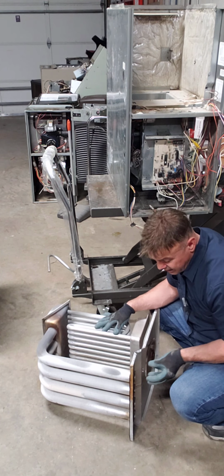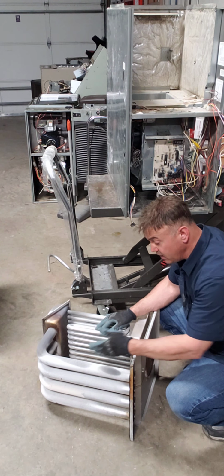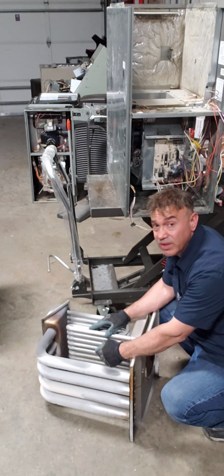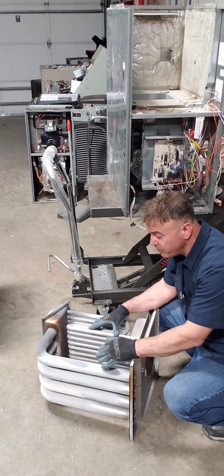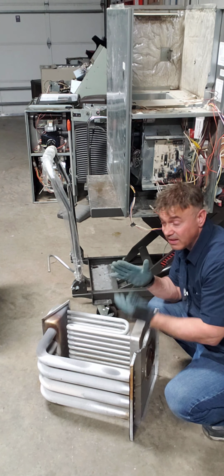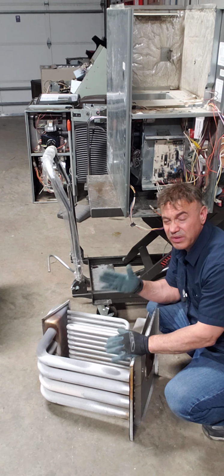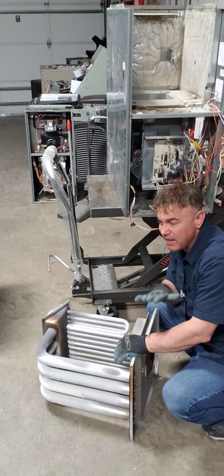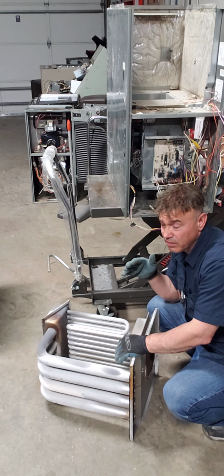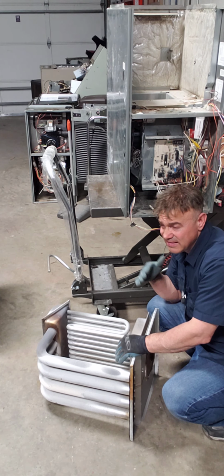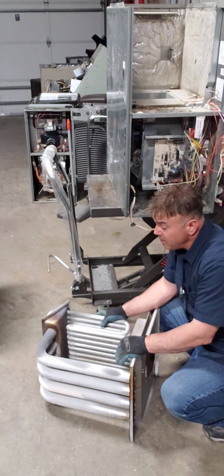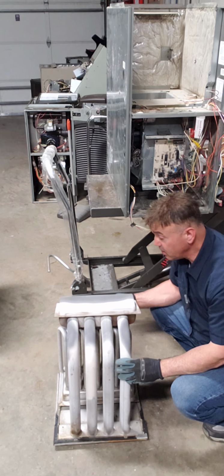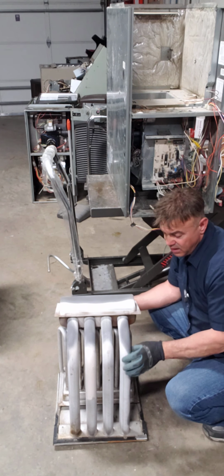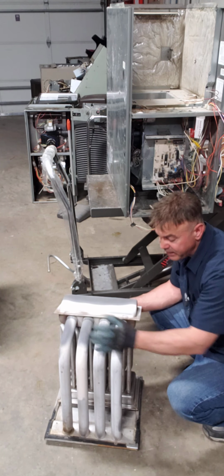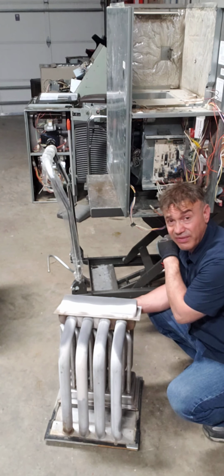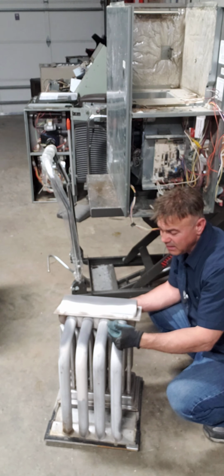With an inducer there's always vacuum, air coming through and out to the motor. If you have a crack here, it will be sucking the fresh air into the combustion, which is safer. That's different from when you have a natural flame going into one path and the air goes and mixes with it. If you have a crack, that's what people used a long time ago, 50 years ago. You hear on the news every year, once in a while, somebody dying. Even now, God forbid, but mostly in places with old systems. So that's why the government pushed for the inducer motor, because it's always a vacuum condition here. No matter how many cracks you have, it's going to weaken the system. It's going to stop. You're going to have a flash code, whatever. But again, it's not going to mix with the fresh air.